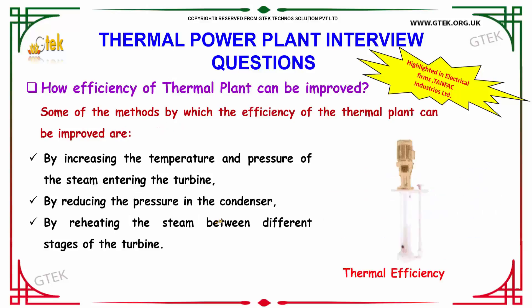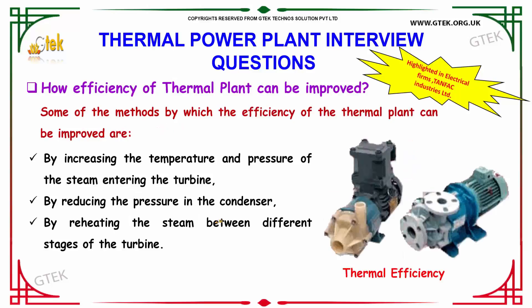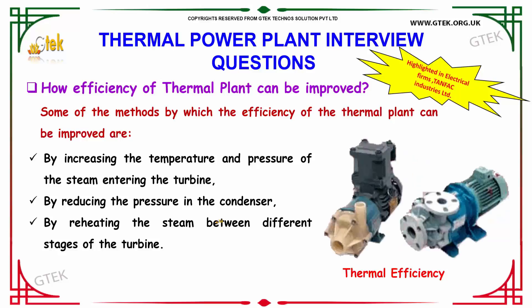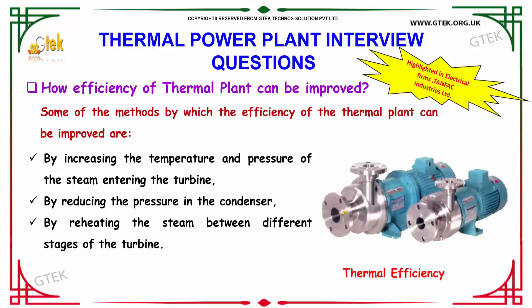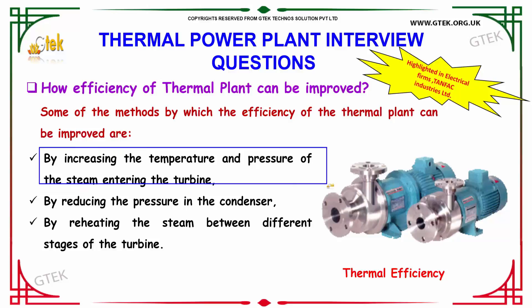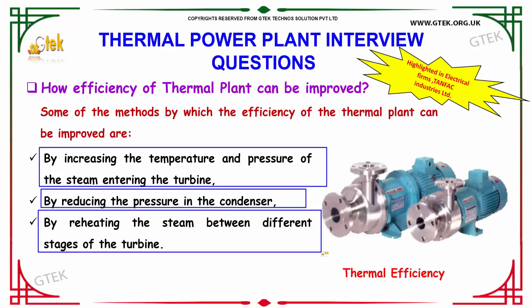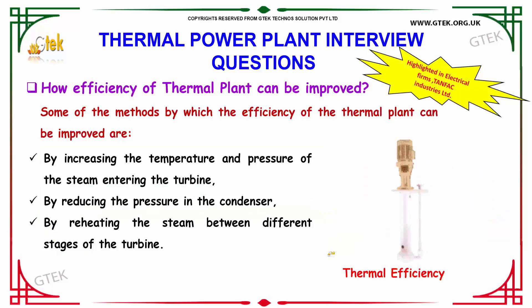How can the efficiency of a thermal plant be improved? It can be improved by increasing the temperature and pressure of the steam entering the turbine, by reducing the pressure in the condenser, and also by reheating the steam between different stages of the turbine.